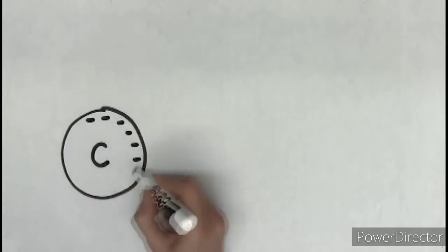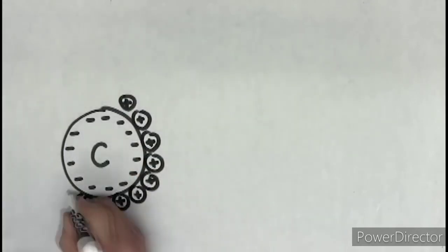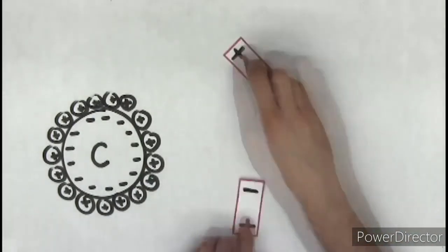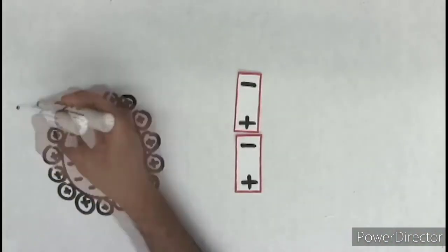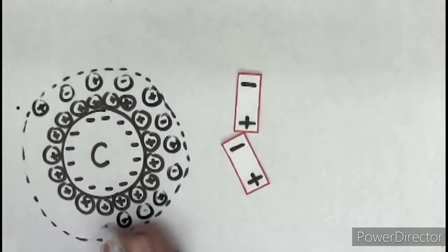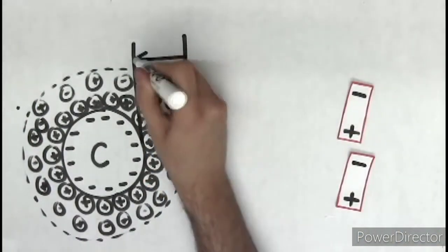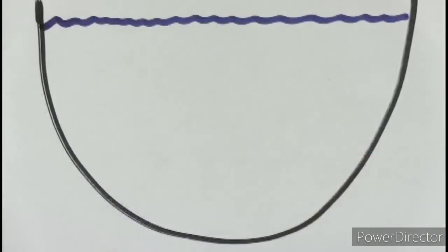So in this process the water is being cleaned. By adding this kind of flocculant we can clean the water. How does the process actually take place? Basically colloids are negatively charged particles, student. So the flocculant, like aluminum sulfate that we are adding, must be a positively charged ion. As we know, the same charge will repel and opposite charges will attract each other. So here the colloid is negative and our flocculant is positive, so they will attract together and form a kind of double layer.